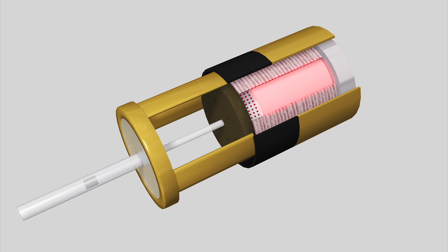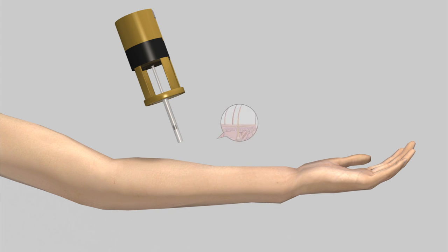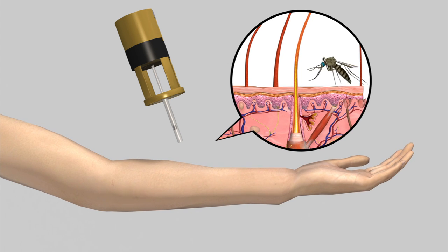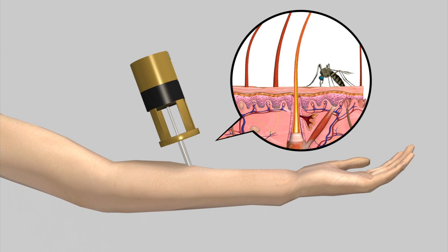The design is based around a magnetically activated actuator. When a current is applied, a powerful magnet surrounded by a coil wire forces the piston forward, ejecting the drug at high pressure and velocity from a nozzle the size of a mosquito proboscis and through the skin.